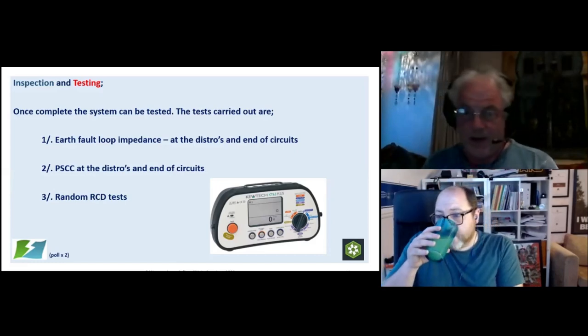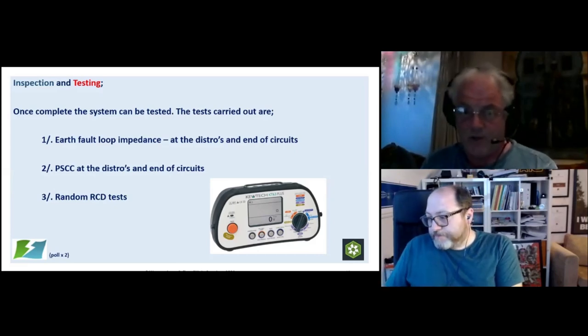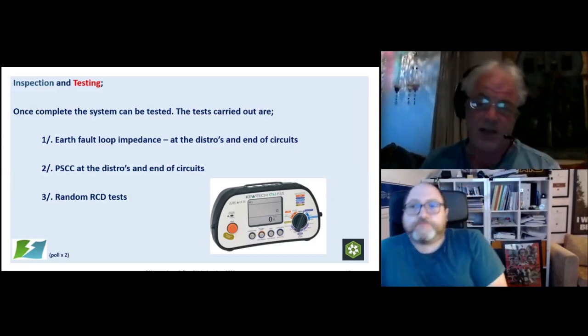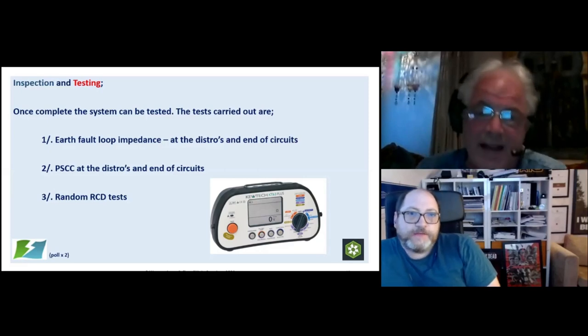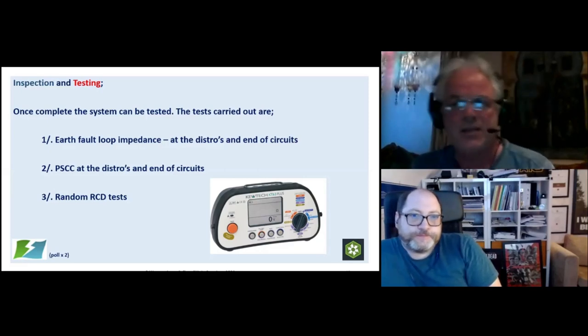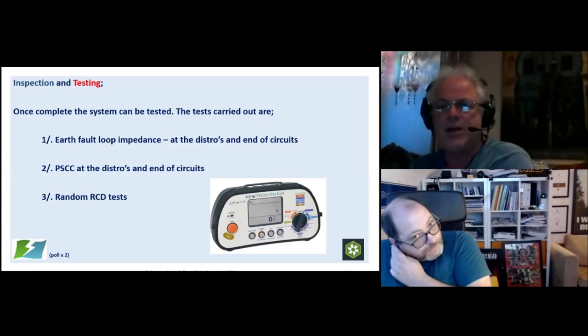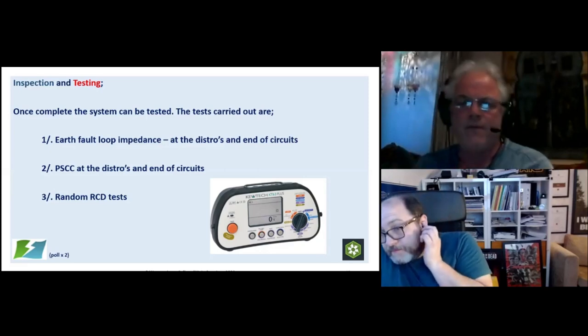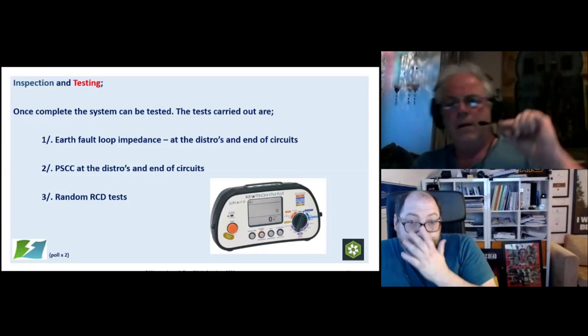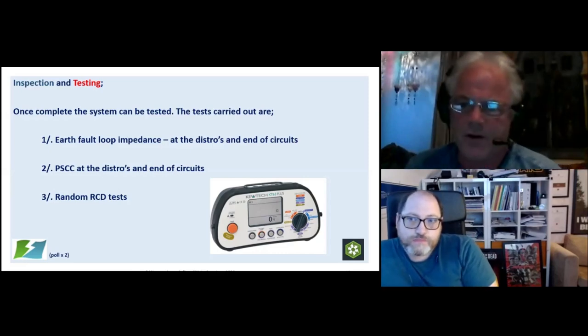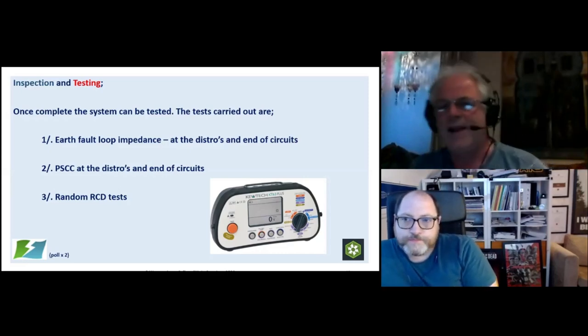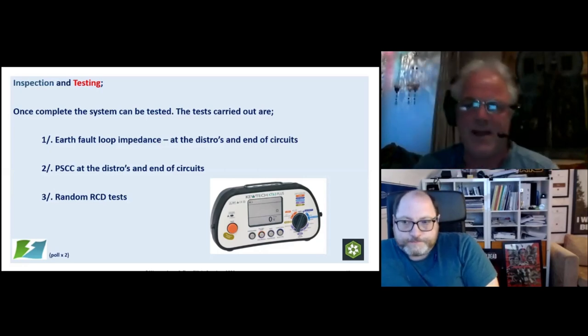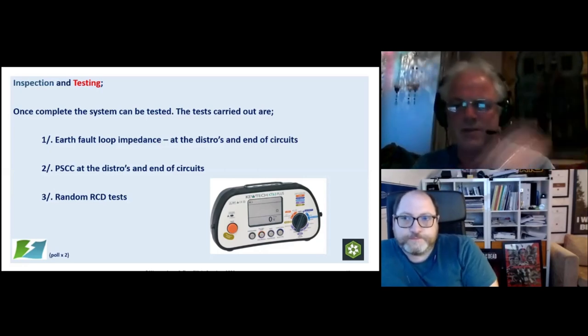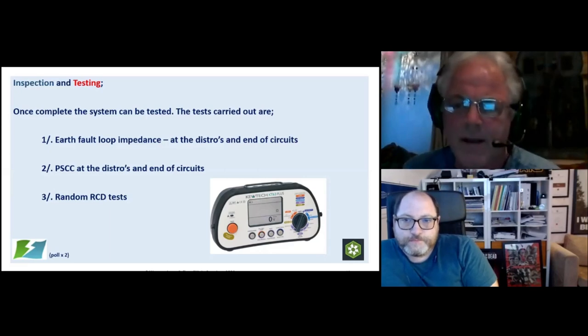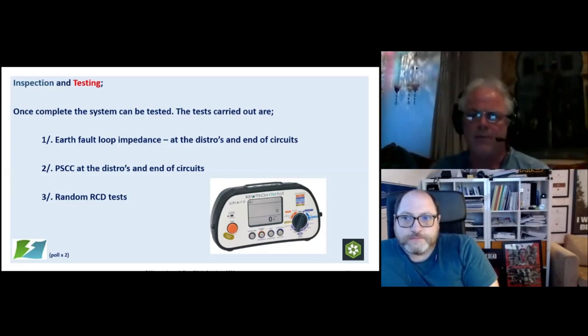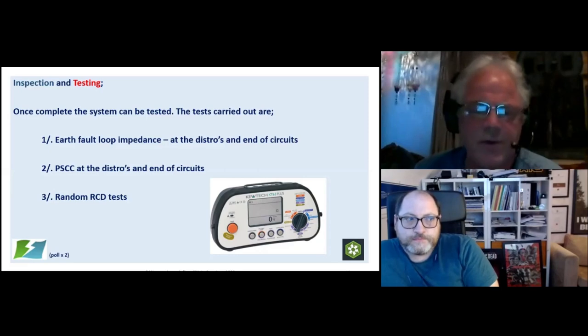So once we're complete, we always test the system. We're looking at doing earth loop at the distros and at the end of circuits. We're looking at doing fault current at the distros and at the end of circuits. Most important that we do fault current at the end of circuits. And that, if you think about it, guys, is because RCDs will provide us with earth fault protection, even if we've got a fairly long circuit. You know, a 30 milliamp RCD, we're looking at 1,667 ohms, and it will still trip before it goes over a 50 volt sort of touch voltage.